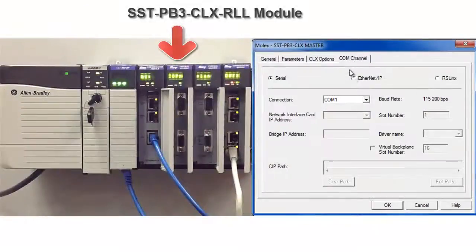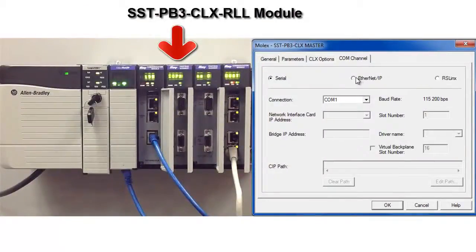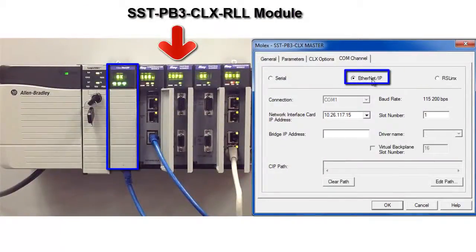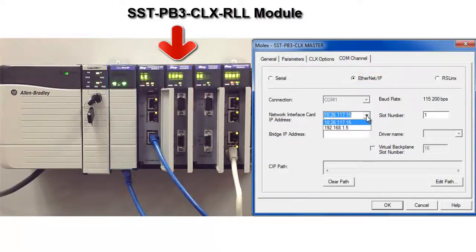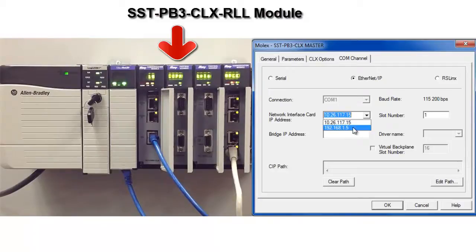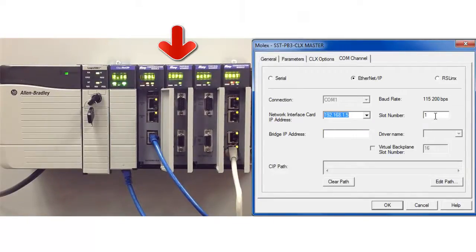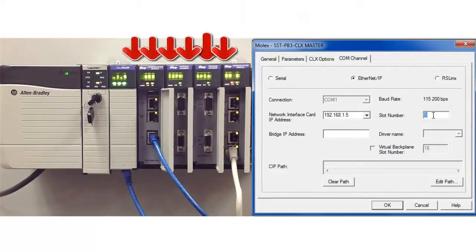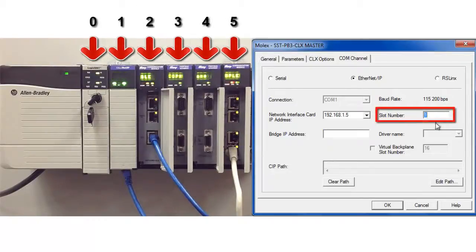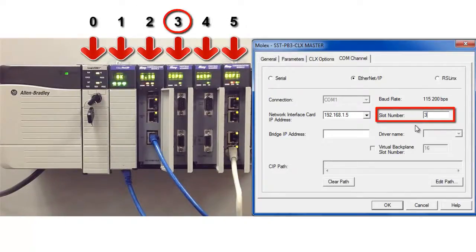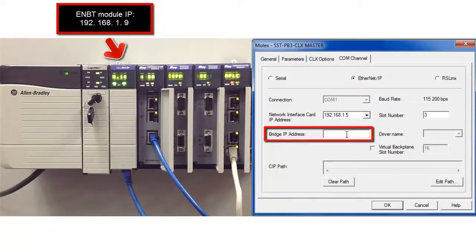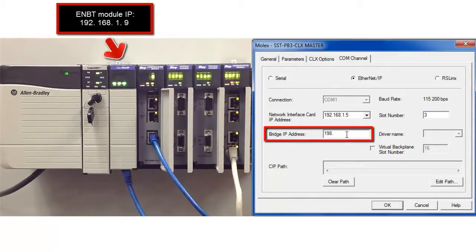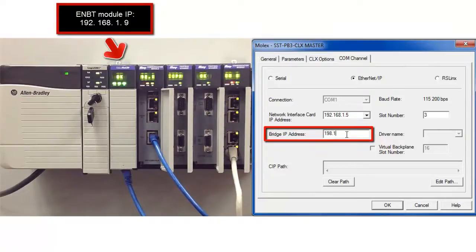And then in the comm channel, we're going to use Ethernet IP to communicate to the module. So the network interface card is the IP address of your PC. In case you have more than one, you have to select it like I do. Slot number is going to be the slot number of our module, which in my case is slot 3. And the bridge IP address is the IP address of the ENBT module in the same rack as our card.